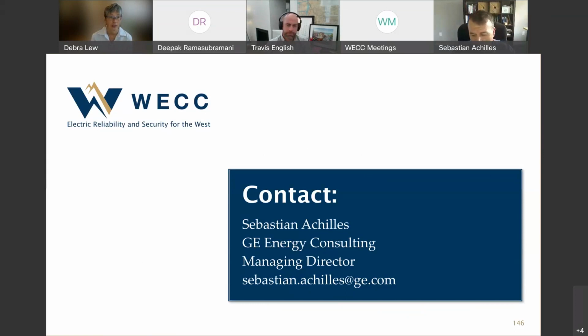That's a good question. That page and discussion in general was conceptual, and I purposely avoided the subject of composite or weighted short circuit ratio. In principle, I'd suggest considering those short circuit ratio numbers as some form of multi-in-feed short circuit ratio calculation, like the weighted or composite short circuit ratio. I think using the simple short circuit ratio calculation when there's more than one source of inverter-based resource is just not recommended, and I didn't mean to imply that. Multi-in-feed concepts like weighted and composite short circuit ratio should be applied in all cases when there's more than one inverter-based resource plant.